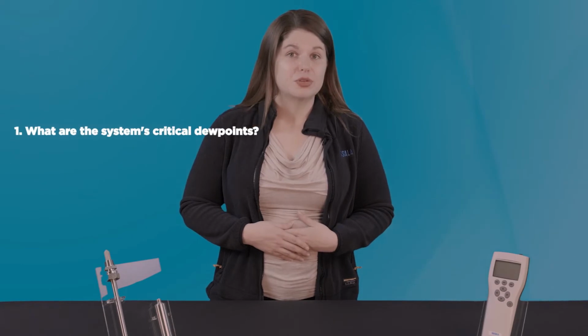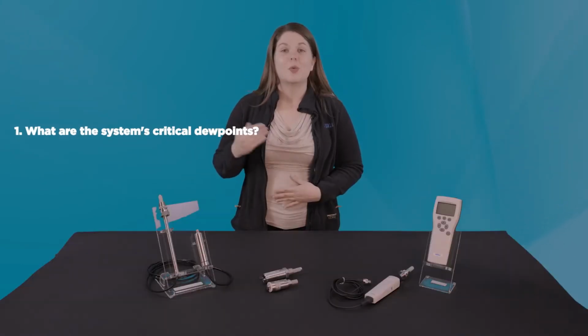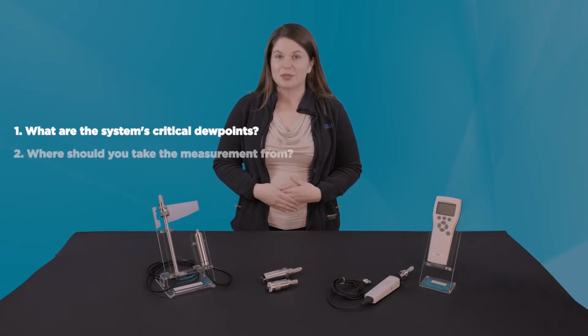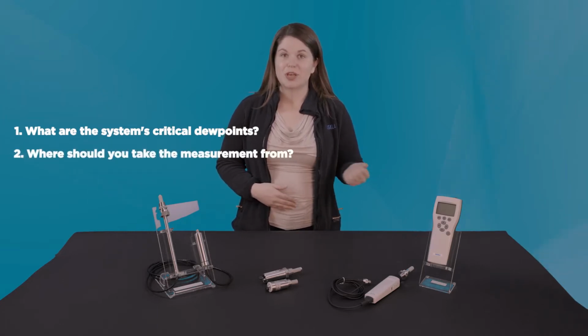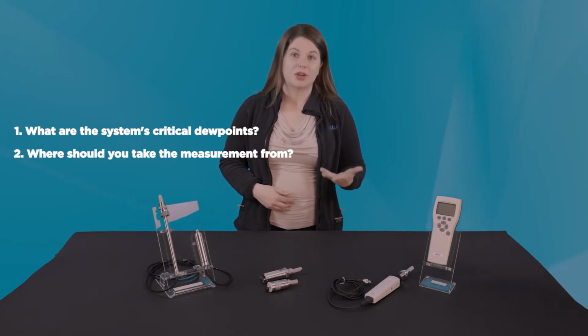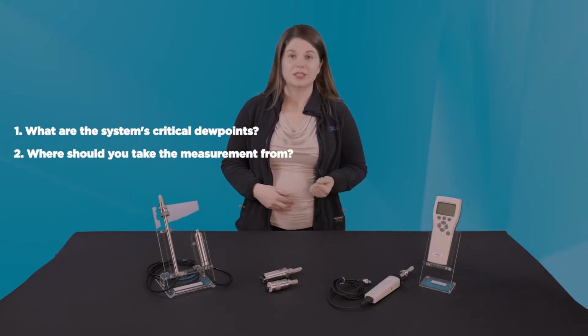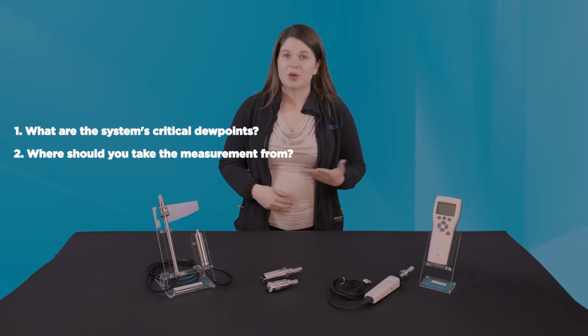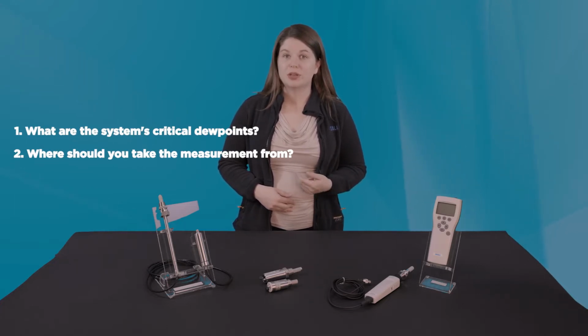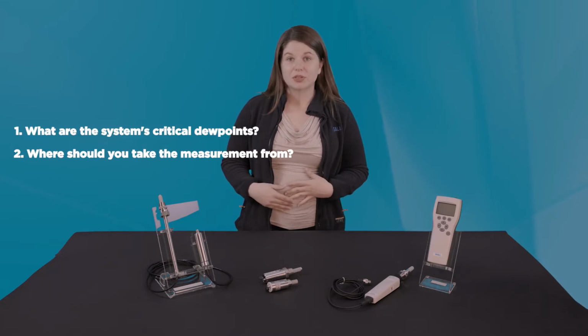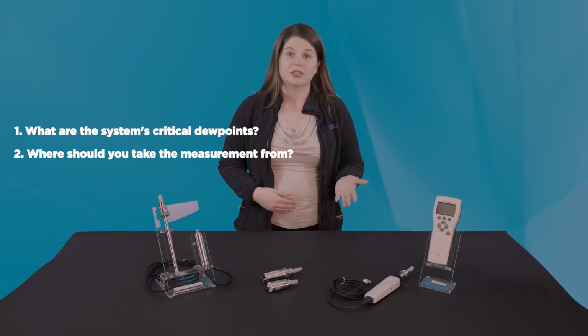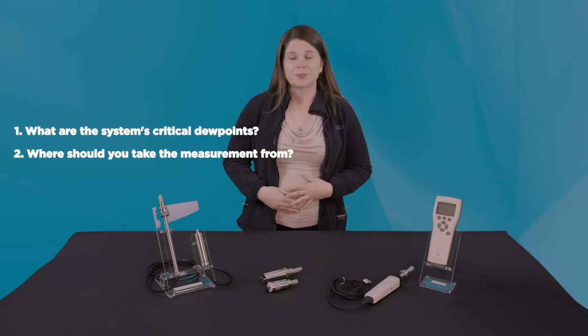So what dew point level is your system being controlled to, or what dew point levels are you trying to avoid? Think about where it makes the most sense to measure from. If your goal is optimizing energy used in a compressed air system, then you may want a dew point sensor at the compressed air dryer outlet. Or if your goal is to ensure product quality in a process involving dry air, you may want a dew point sensor at the point of use.